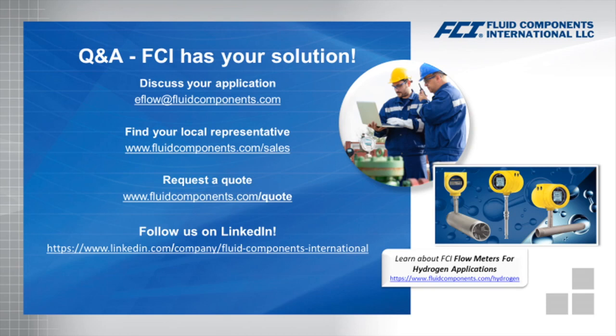I'm not sure I fully understand that one, Katie, but I think what we're getting at is, when you're installing an instrument into the process, what kind of sealing methods. Typically, in these applications, you're going to look at products with either flange connections or a compression fitting, maybe with a metal ferrule, because your concern there would be any kind of loosening of that connection, potentially hydrogen leaking into the atmosphere. If that's not the answer, I can get back to them later.